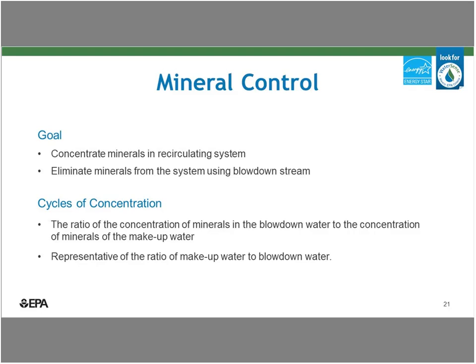The reason for the blowdown is to keep minerals or dissolved solids from building up in the tower and possibly causing issues like scale. As you can see in this example, city water contains dissolved solids. As water evaporates, these solids stay in circulation and begin to get more concentrated over time. If the concentration gets too high, the solids will begin to form scale on the surfaces of the chiller system, which can then degrade performance or damage the equipment. Therefore, some water is regularly discharged, and this is blowdown, and it's meant to keep the dissolved solids in check. This blowdown is typically controlled by a conductivity meter or controller, and careful blowdown control offers really the best opportunity for savings in the cooling tower system.